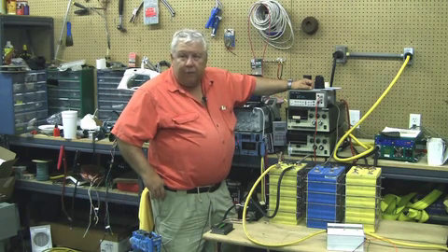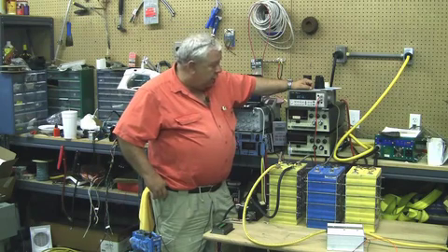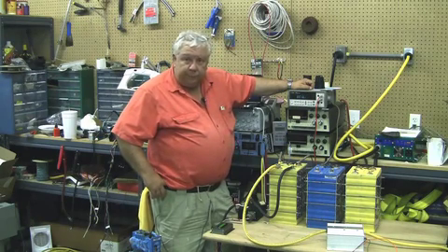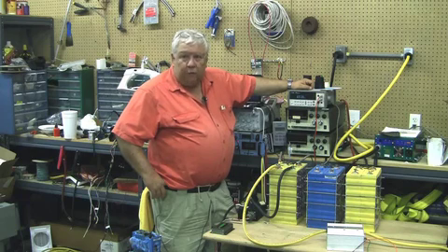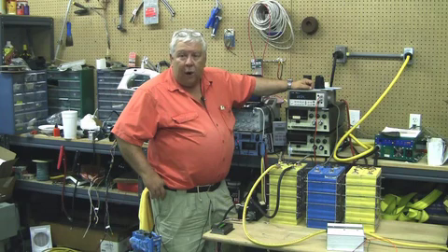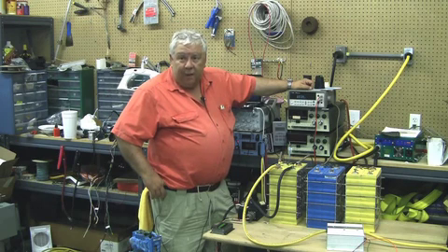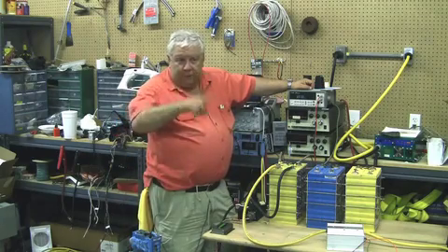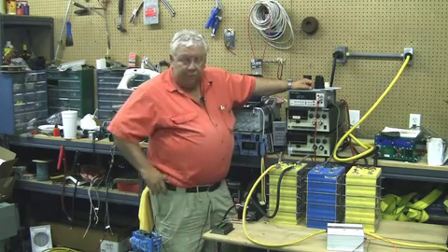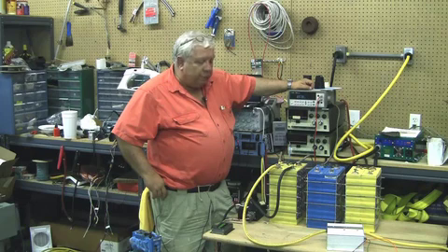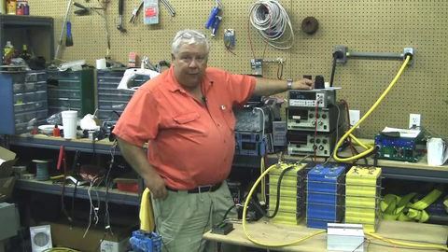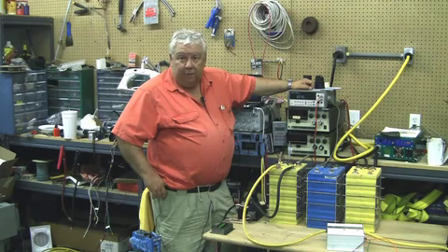And by stepping up to a 4-cell voltage, I can run 3C. And we're going to do a pulse test. We'll take out a couple of amp hours in a pulse and then let it rest for a minute. And take the voltage after it's rested and after it's taken a couple of amp hours out, and do that 30 or 40 times and do us a little sawtooth diagram to see what voltage sags we see at 3C and what the temperature does under those kind of loads.